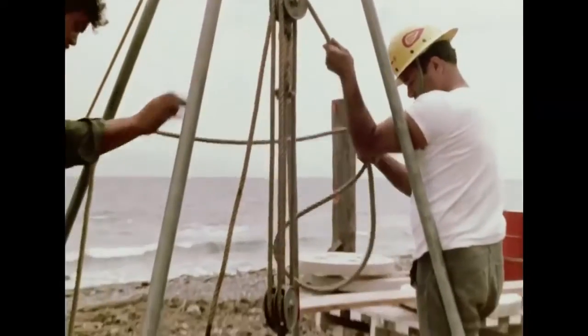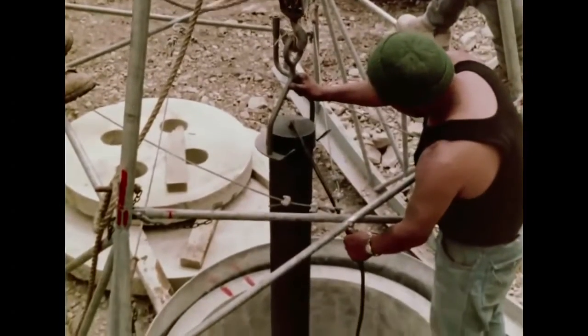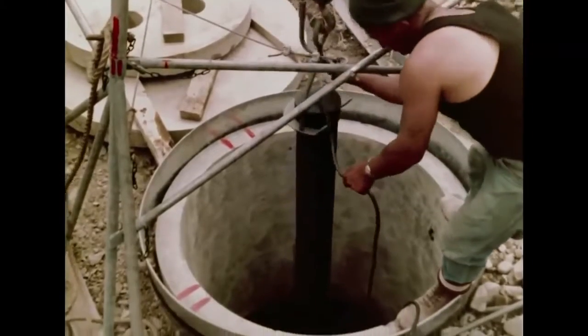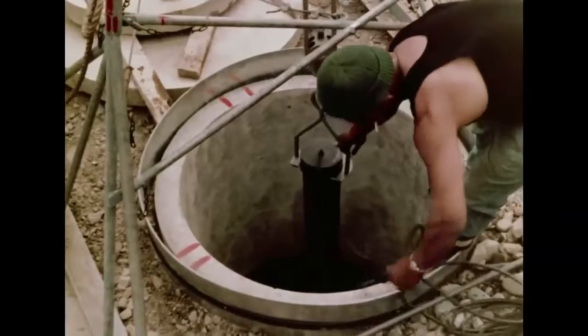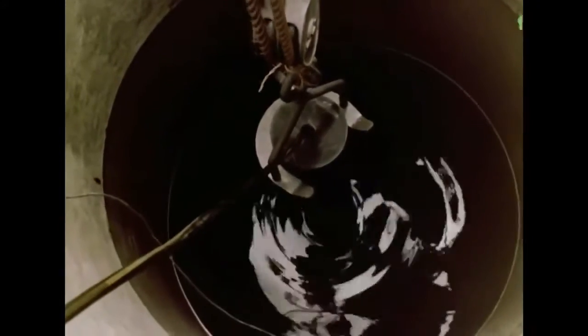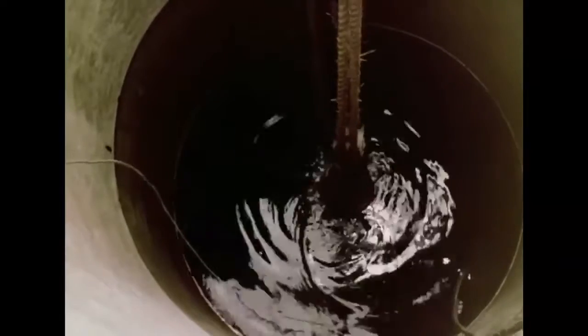Into each of the 25 vertical pipes, a 7-foot-long graphite electrode is lowered. These are 6 inches in diameter, and the 25 of them can pass enough current into the sea and back to electrodes at Benmore to provide an earth return for the current from any one of the 3 Cook Strait cables. Even if 2 of the 3 submarine cables should be out of action, the scheme can still function on part power.